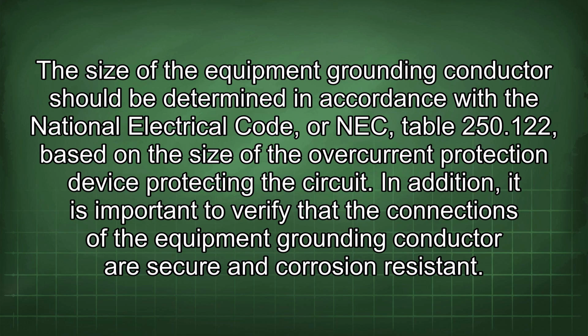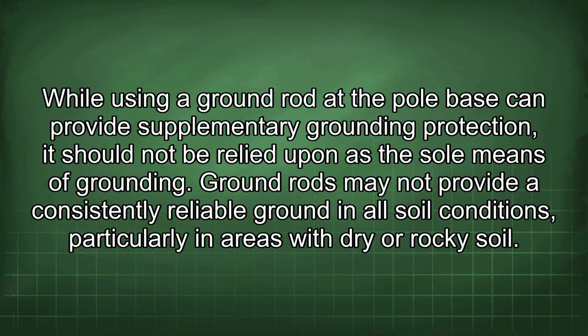The size of the equipment grounding conductor should be determined in accordance with the National Electrical Code, or NEC, Table 250.122, based on the size of the overcurrent protection device protecting the circuit. In addition, it is important to verify that the connections of the equipment grounding conductor are secure and corrosion resistant. While using a ground rod at the pole base can provide supplementary grounding protection, it should not be relied upon as the sole means of grounding.